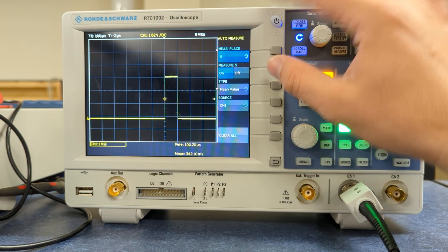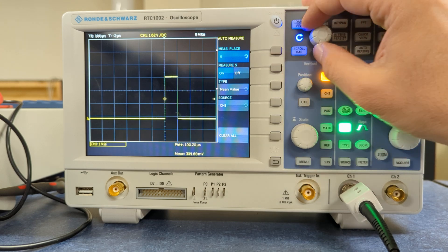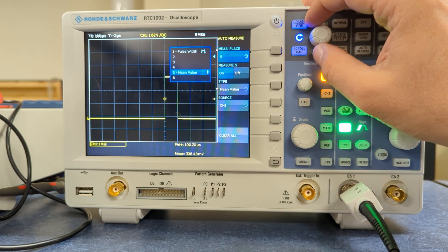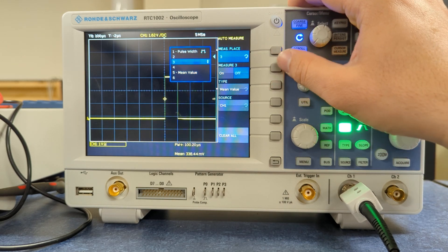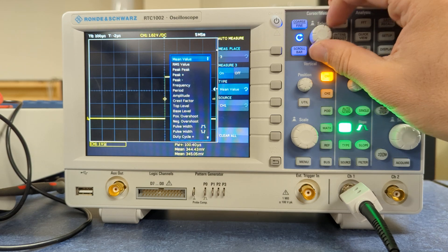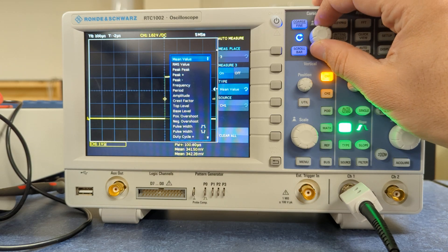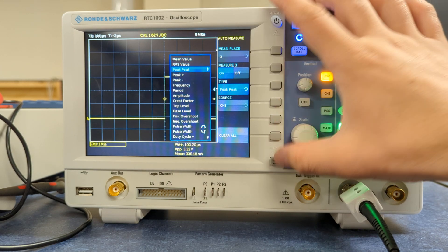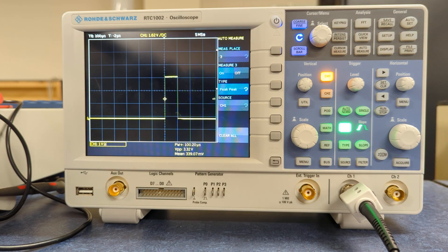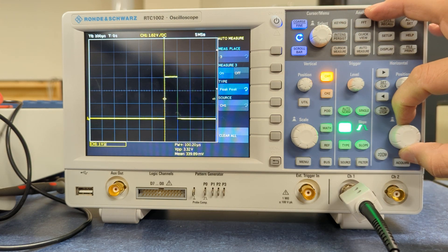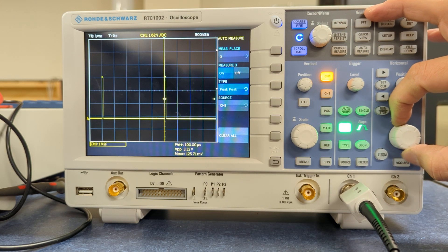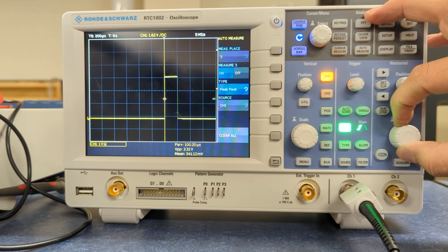So all that you do is you select the measurement you want, and you can turn it on or off. So you can see here, there's some other mean value. I could say, hey, what's measurement three? Let's turn that one on. And let's make that, I don't know, positive peak. So you can get a bunch of measurements and statistics up on the bottom there. So that's it. So that's how you do some quick setup with this scope and get used to using it.